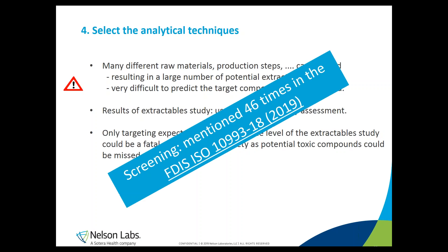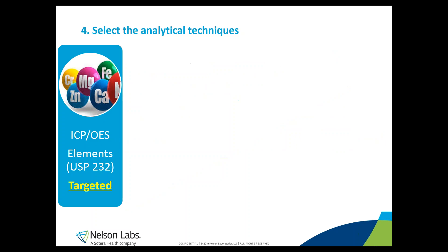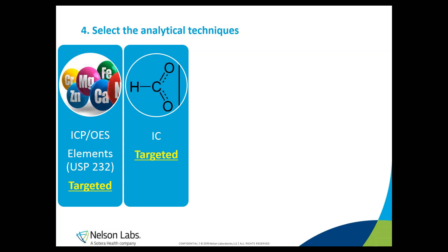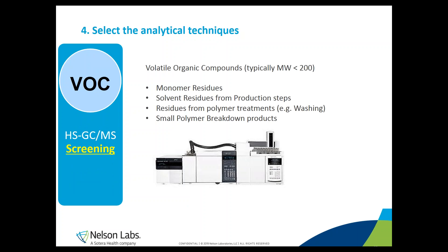Does that mean you only need to use screening methods? No, but screening is becoming more important — mentioned 46 times in the final draft. Targeted methods can be used for a limited set of compounds, such as elements targeted according to USP 232, or ions captured by ion chromatography. For organic compounds, however, there is such a large population ranging from very small to very large, from polar to very apolar, that it is advised to use at least three different analytical techniques.